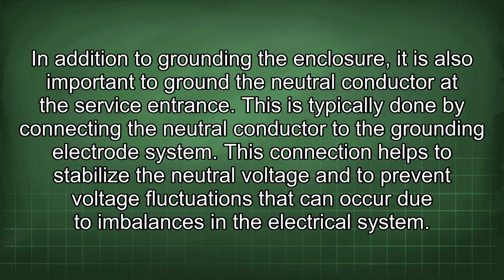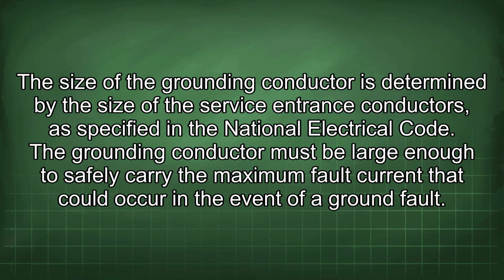This connection helps to stabilize the neutral voltage and to prevent voltage fluctuations that could occur due to imbalances in the electrical system. The size of the grounding conductor is determined by the size of the service entrance conductors, as specified in the National Electrical Code.